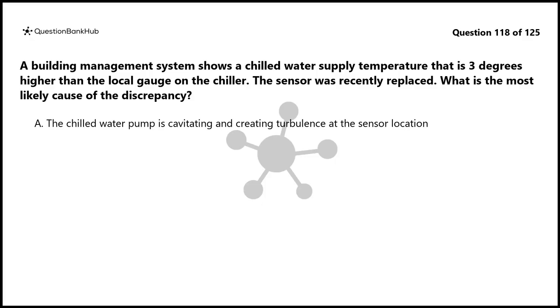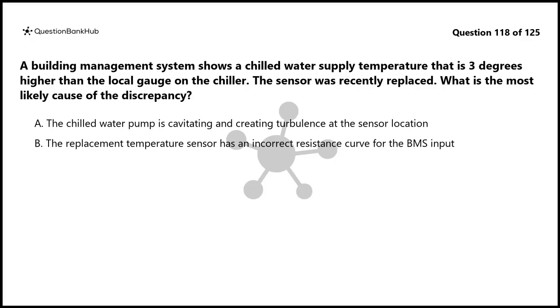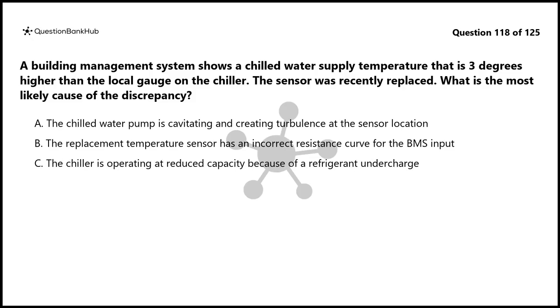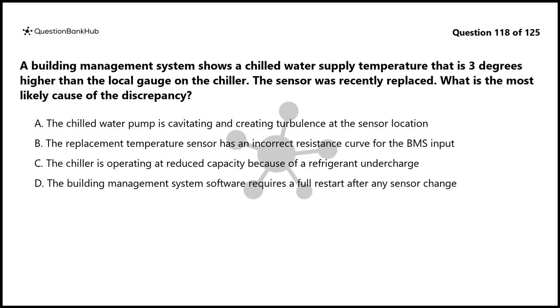A. The chilled water pump is cavitating and creating turbulence at the sensor location. B. The replacement temperature sensor has an incorrect resistance curve for the BMS input. C. The chiller is operating at reduced capacity because of a refrigerant undercharge. D. The building management system software requires a full restart after any sensor change.